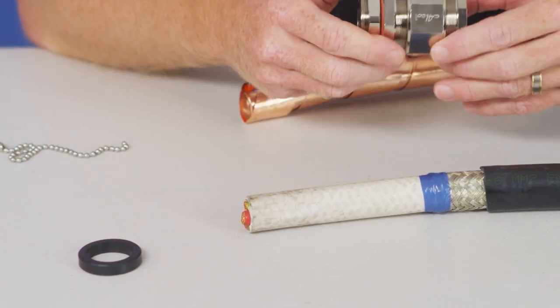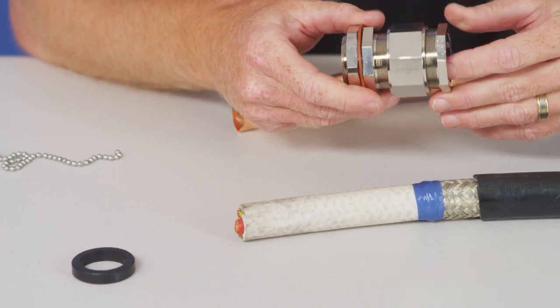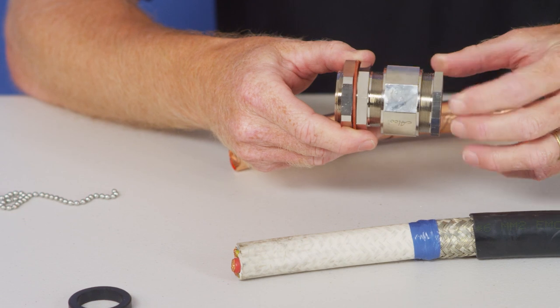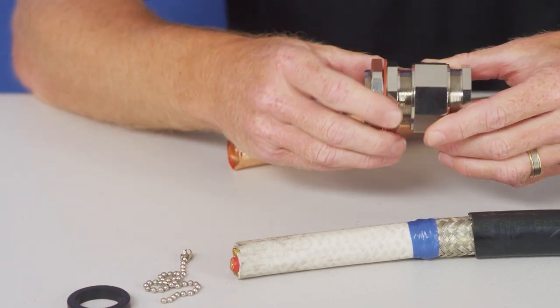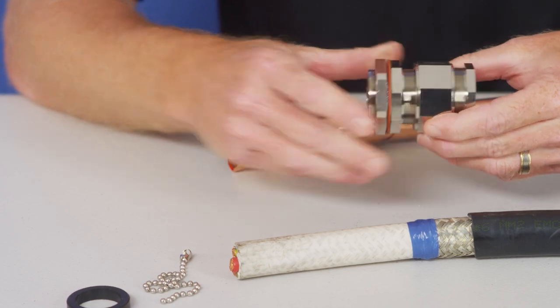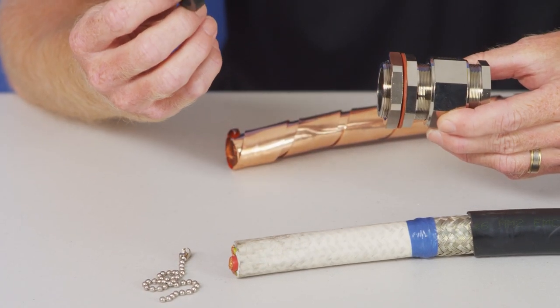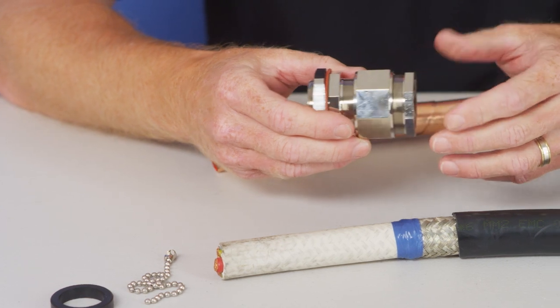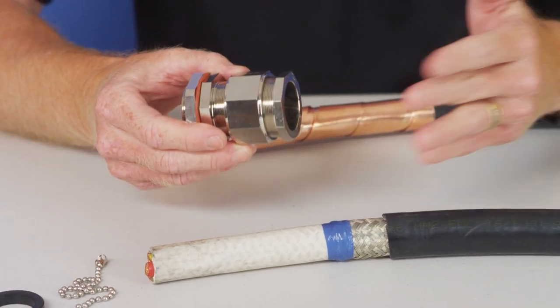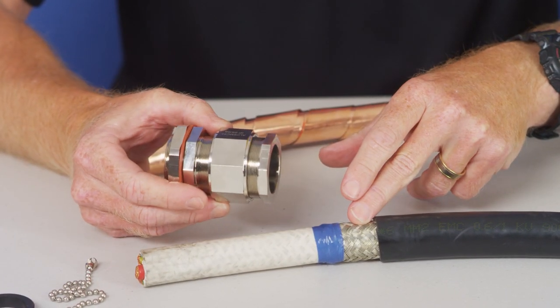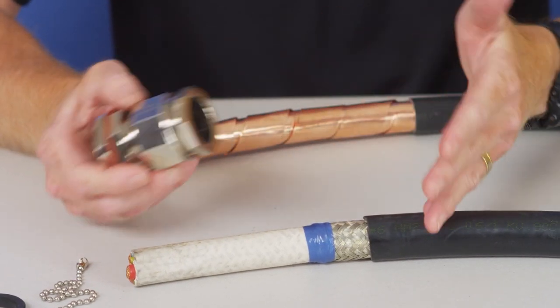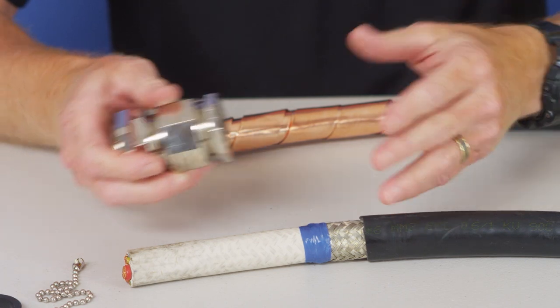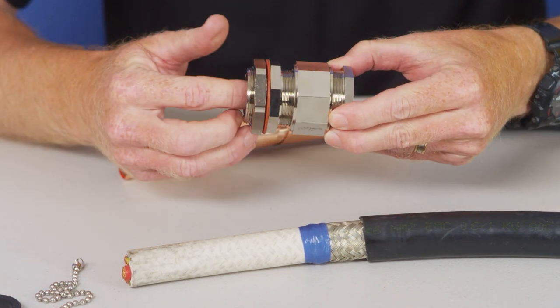The second style of EMC gland that we're going to show today is the Alco Premium style. Now this one here comes in several different parts and it also comes with two seals. So when you go to use the gland you've got to determine the outside diameter, the over braid diameter and then you select the right type of gland. And obviously we've prepared this cable earlier and we've determined what gland we use.